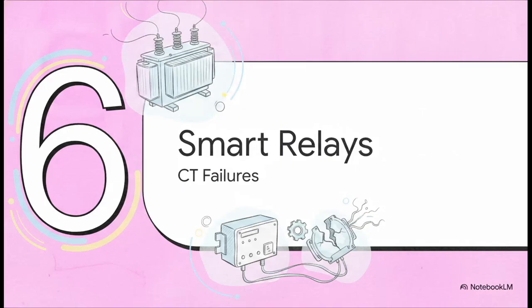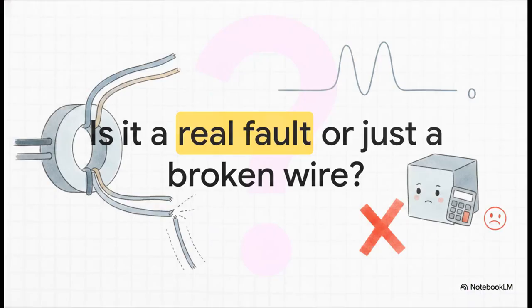Finally, Section 6, Smart Relays and CT Failures. This brings us to our last major hurdle. What happens when the relay's own monitoring equipment breaks down? The relay gets all of its intel from current transformers, or CTs. But what if a secondary wire on one of these CTs just accidentally snaps? The current reading on that phase is going to instantly drop to 0.